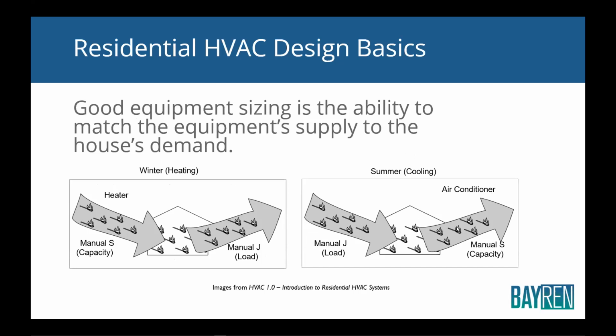But the challenge is, like I mentioned, the actual design capacity of an air conditioner is not the same as what we call the nominal capacity. So if we say, oh, that's a 2-ton air conditioner, if you look up the definition of a ton, it's 12,000 BTUs per hour. But that's the nominal capacity. That's the capacity of that air conditioner under very precise test conditions. So they call it the 2-ton air conditioner. But when you take that 2-ton air conditioner and you put it in a really hot climate, it won't give you 24,000 BTUs of cooling. It'll give you something less than that. And then there's this other thing with latent and sensible capacities, and that all comes into play. So it's a little challenging to actually determine the right design capacity of an air conditioner. And that's why Manual S is so important, okay?